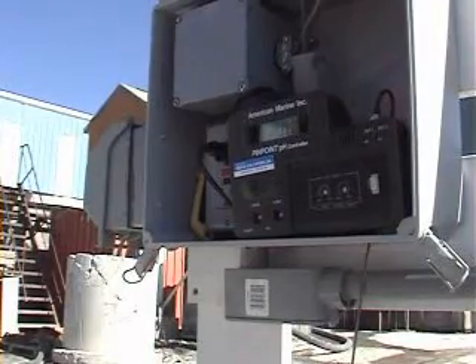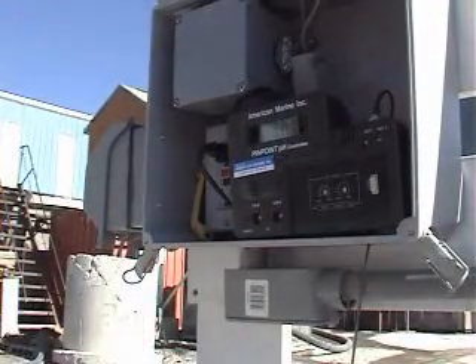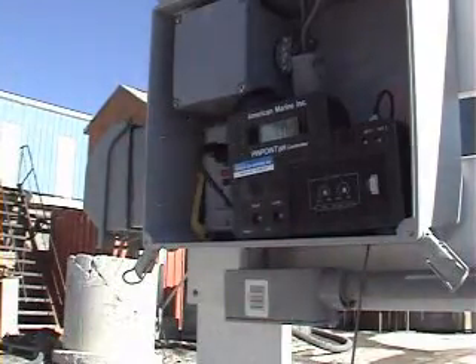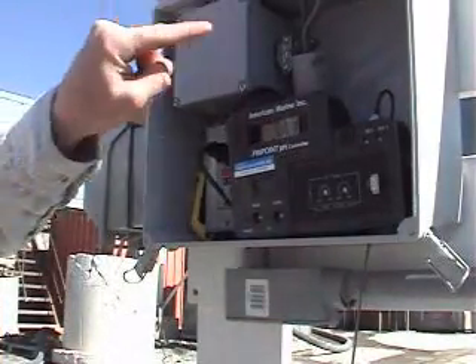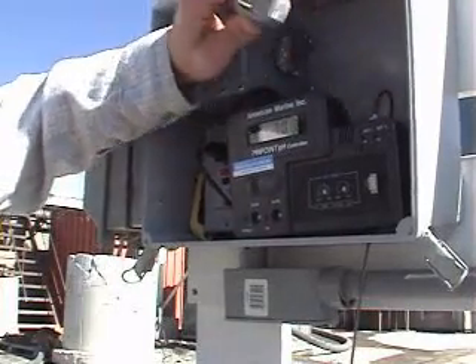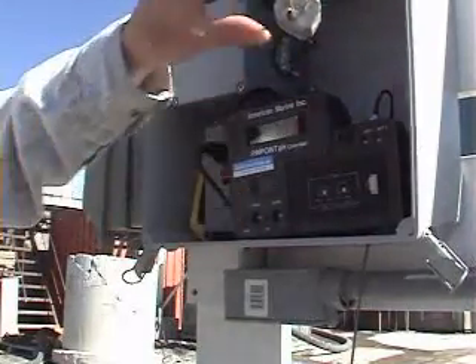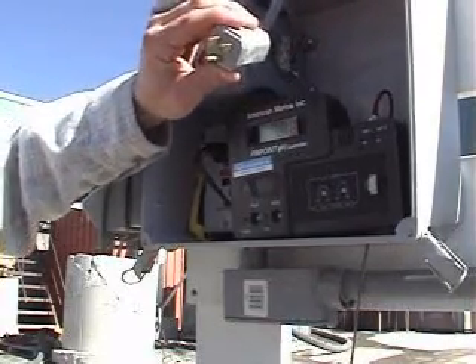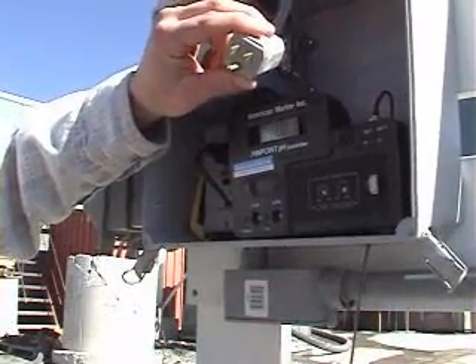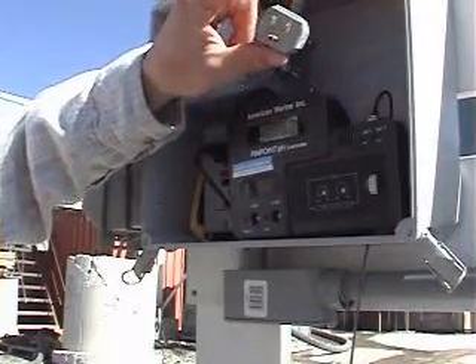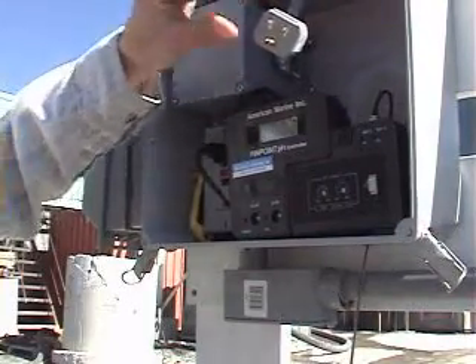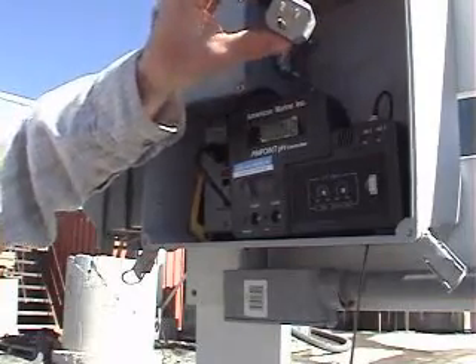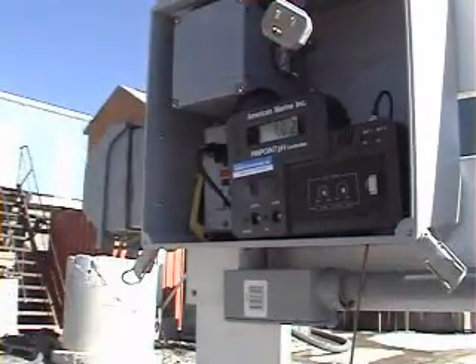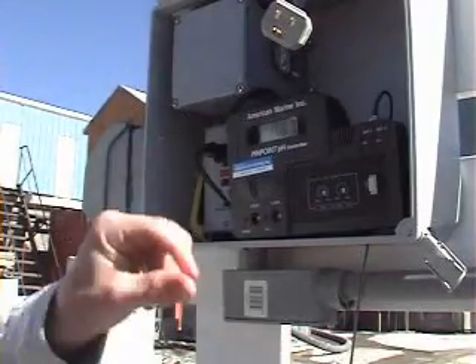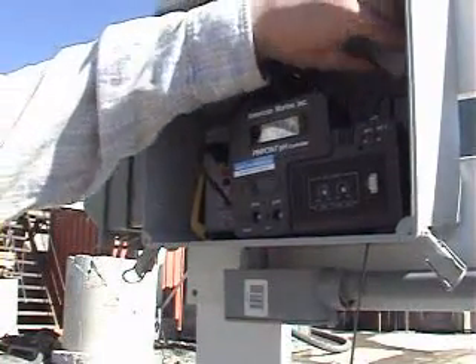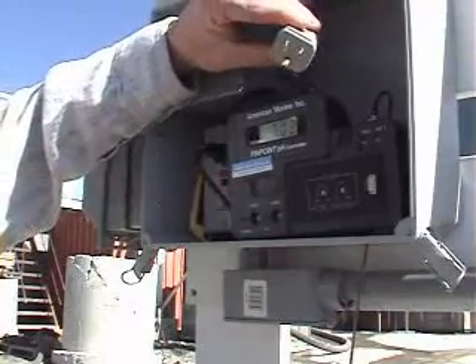Now that I've done that, I'm going to insert the probe into our 10 solution here. But before I do, I just want to double check. This plug here actually feeds directly into the relay. When the pH controller picks up a pH higher than our preset limit, generally around 8.5, 9, this is what actually triggers the relay to turn the pump on. The reason I'm unplugging this is because when I put the probe into the 10 solution here, the pH unit will actually pick that up, and with this plugged in, will actually activate the pump.